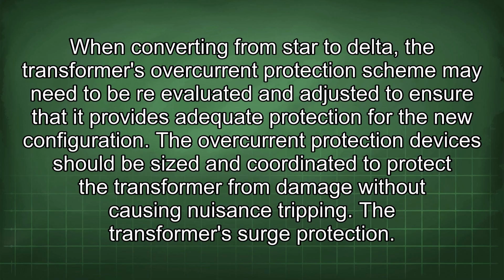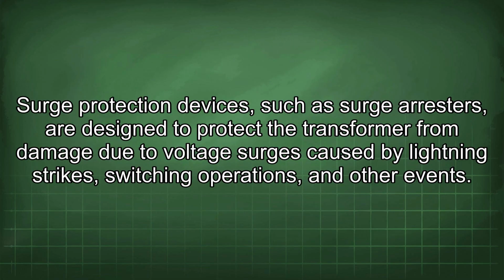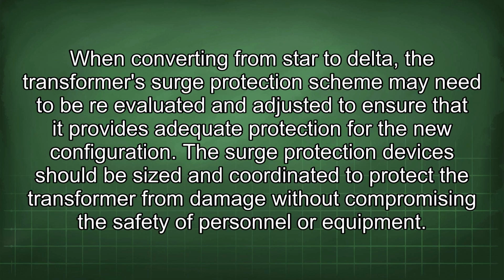The transformer surge protection. Surge protection devices, such as surge arresters, are designed to protect the transformer from damage due to voltage surges caused by lightning strikes, switching operations, and other events. When converting from star to delta, the transformer's surge protection scheme may need to be re-evaluated and adjusted to ensure that it provides adequate protection for the new configuration. The surge protection devices should be sized and coordinated to protect the transformer from damage without compromising the safety of personnel or equipment.